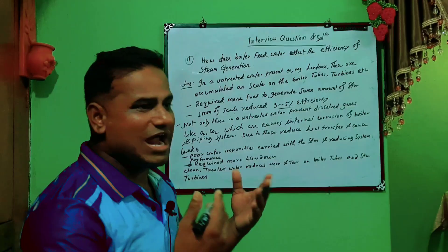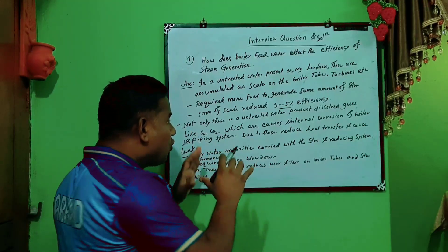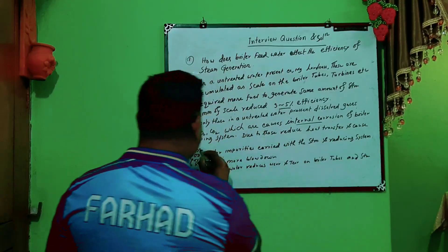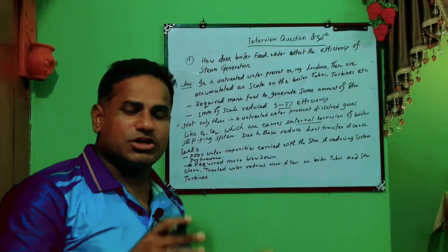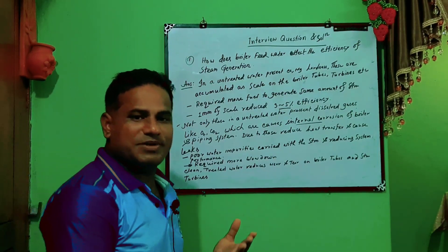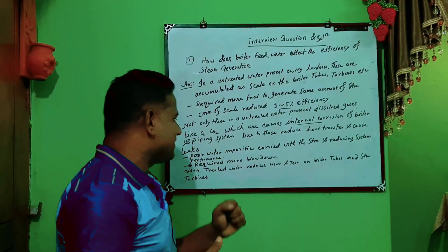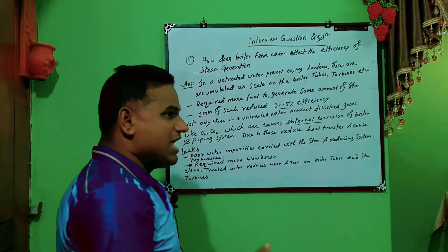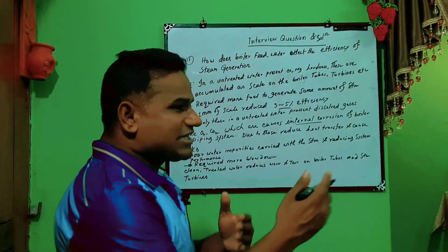The second issue: untreated water contains dissolved gases like oxygen and carbon dioxide, which cause internal corrosion of the boiler and piping system. Due to this corrosion, heat transfer is reduced and leakage can occur.